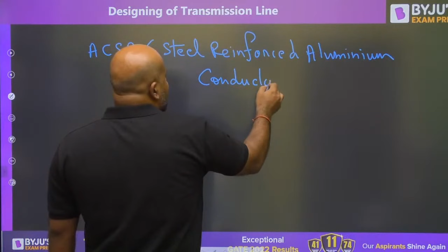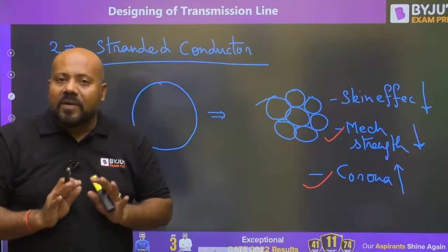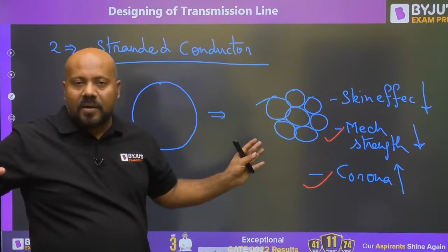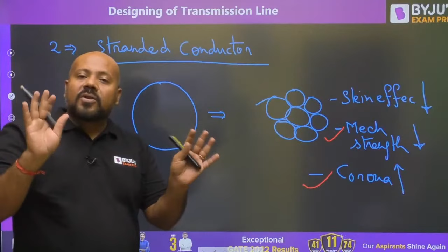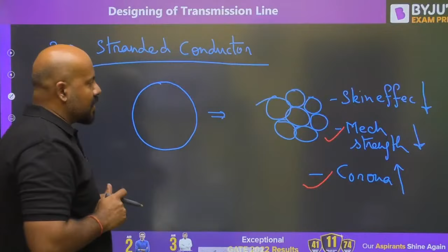I told you that in this stranded conductor, skin effect is reduced, not removed. It means the core strand is still not going to have any significant current. So what I am going to do is remove this core strand, that is aluminum, and place a steel strand. A steel strand is not going to carry any current, but it is going to give you mechanical strength to your conductor.